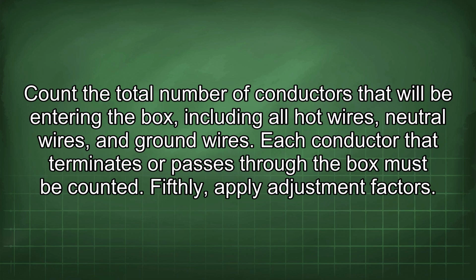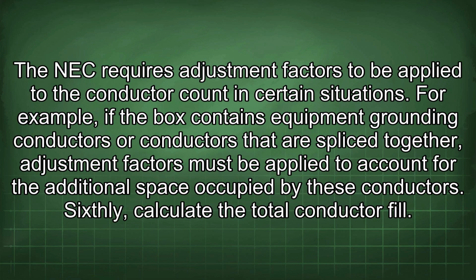Fifthly, apply adjustment factors. The NEC requires adjustment factors to be applied to the conductor count in certain situations. For example, if the box contains equipment grounding conductors or conductors that are spliced together, adjustment factors must be applied to account for the additional space occupied by these conductors.